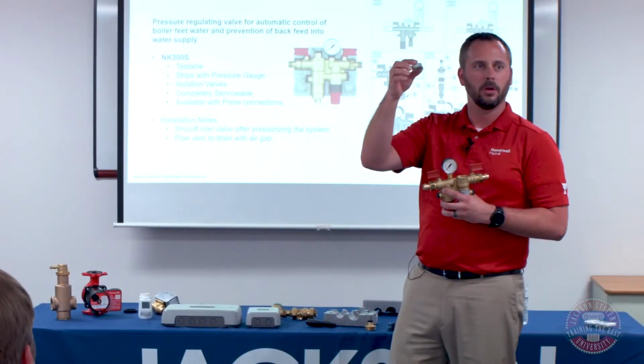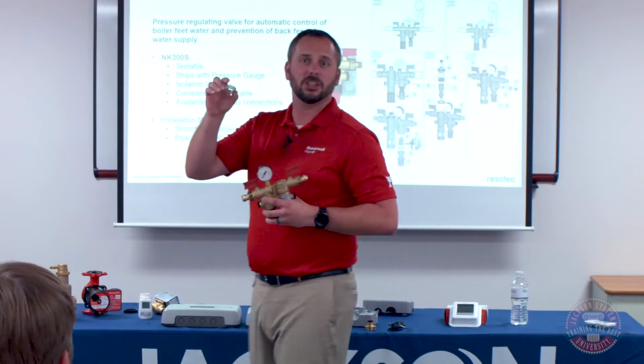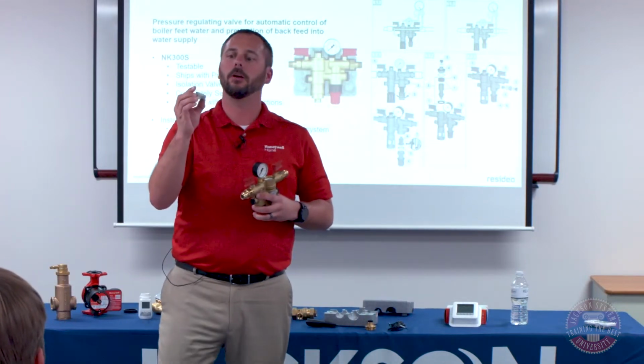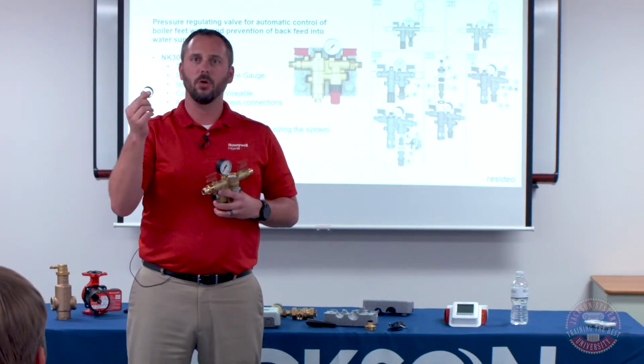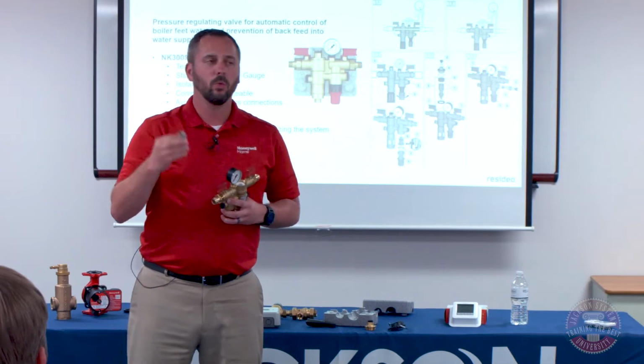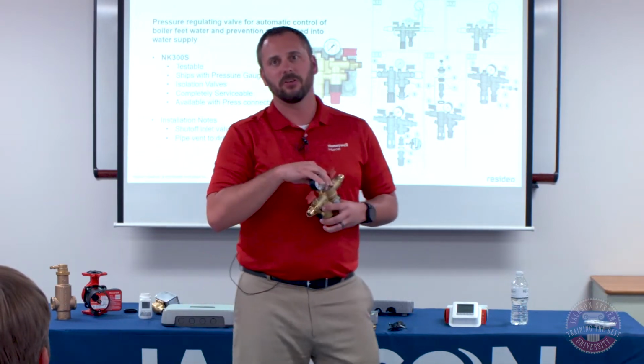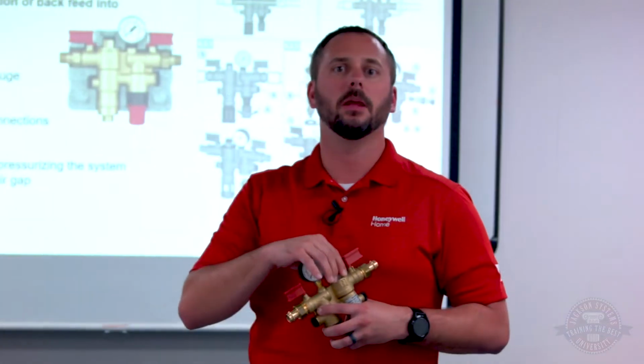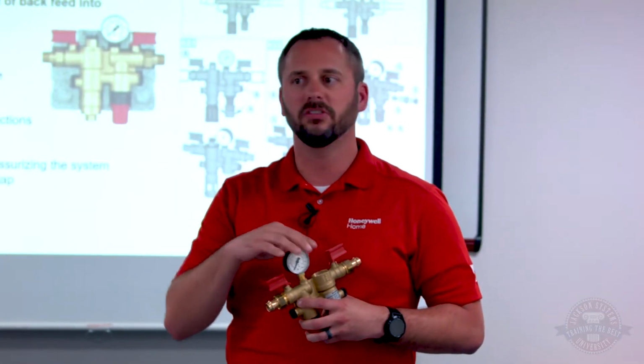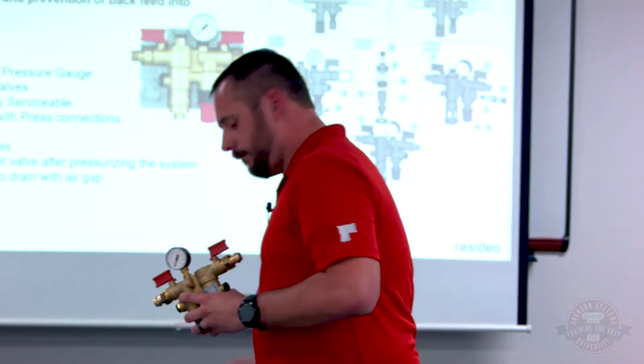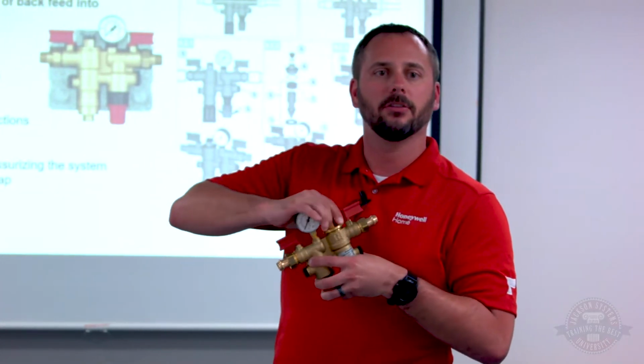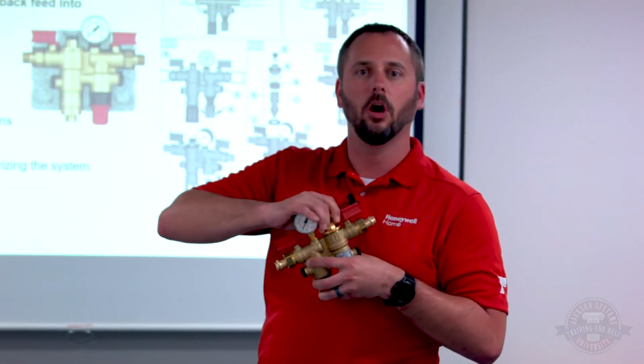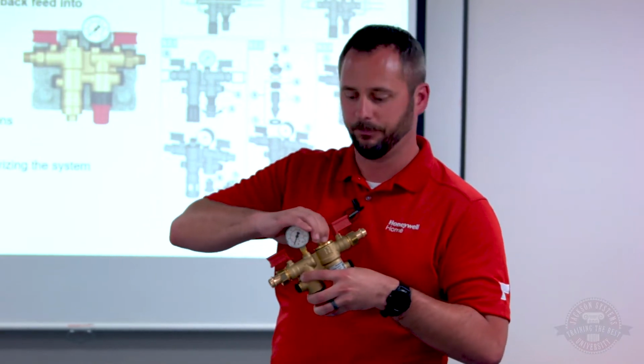One of the big things, you also have access to the sediment screen. So we went with a much finer mesh because we've got bigger surface area on here. So what you're looking at with this is a 200 micron sediment screen. We made a rolling change from the industry standard of roughly 500 micron, and that eliminated a lot of the problems that we were getting with sediment coming in and kind of trapping the valve open. But it's nice to be able to take this all apart without having to run and replace it and hope you can get threads matching back up again.